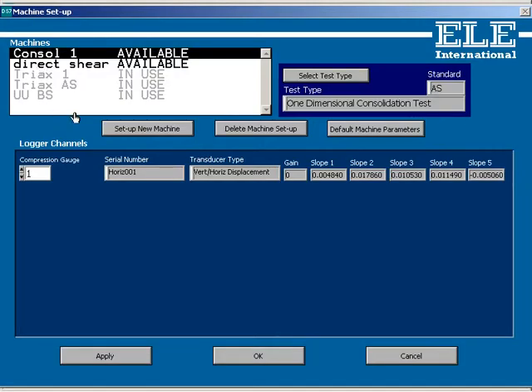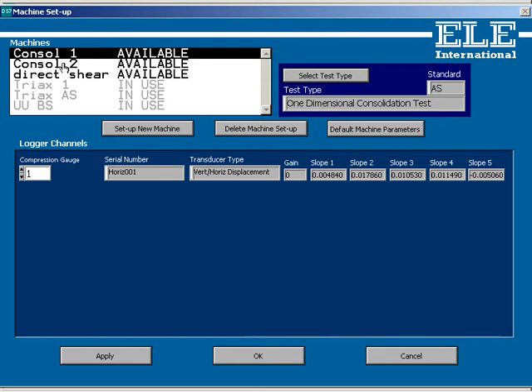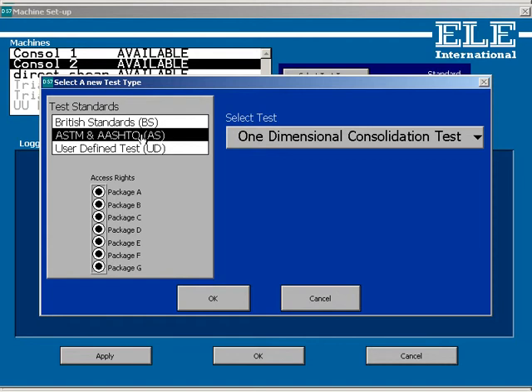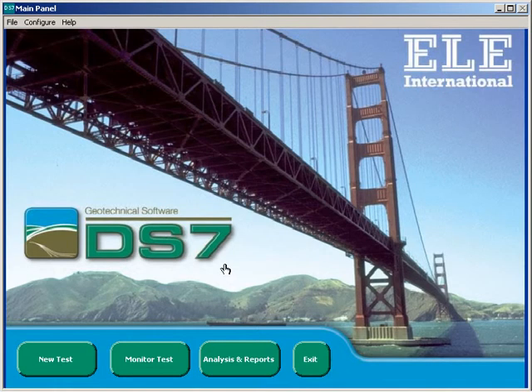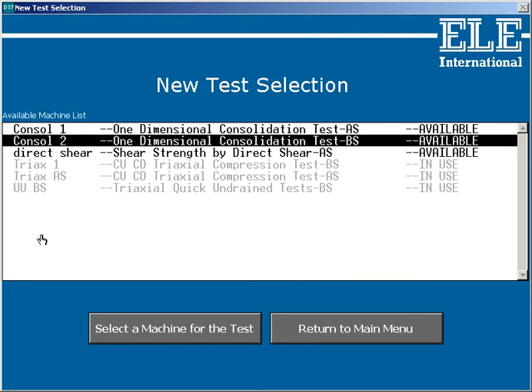We already have one called Consol 1, so we'll set up a new machine and give it the name Consol 2 — second consolidation machine. We then need to select the test type. In this case it's a one-dimensional consolidation test, and the standard we'll use is British Standard. Select the transducer that we previously connected, check that all is well and OK that. In just less than one minute we've set up our new machine which is now ready for a new test. Pressing the new test button shows the new machine on our list of machines ready for testing.